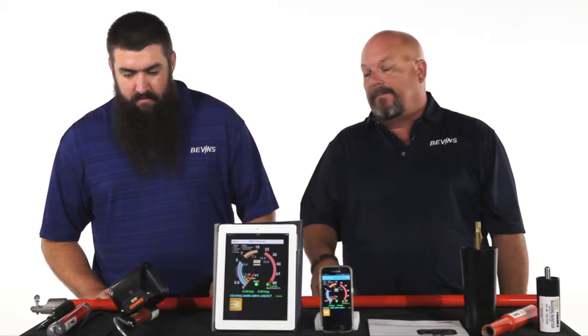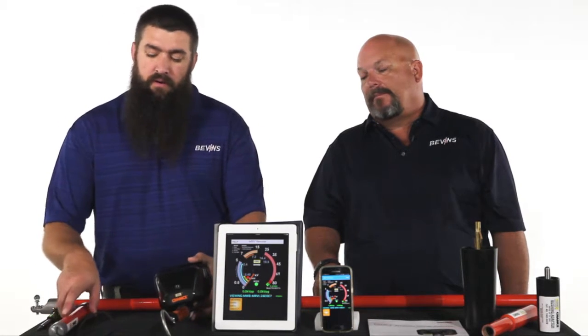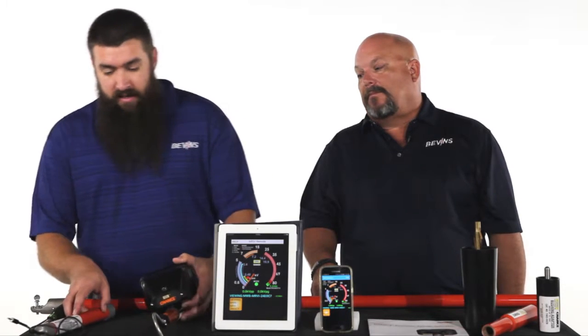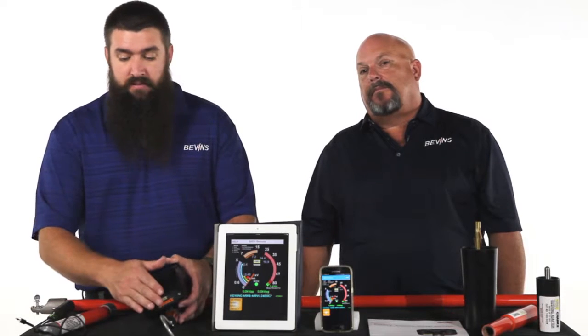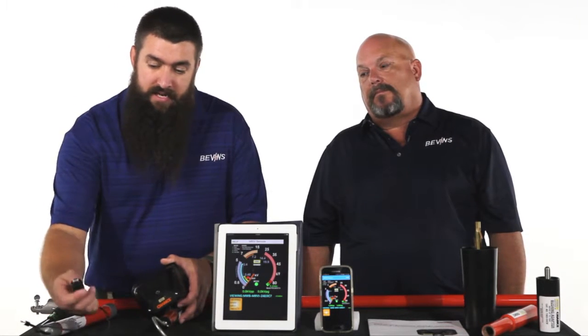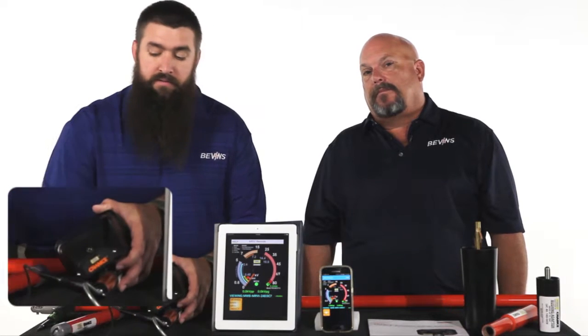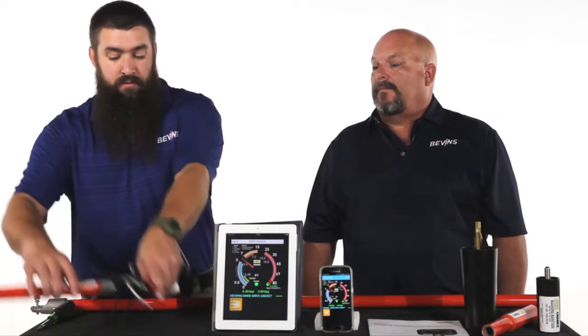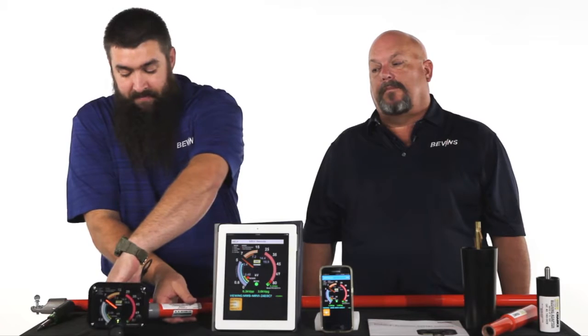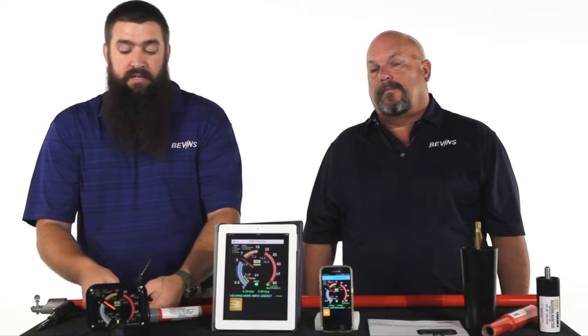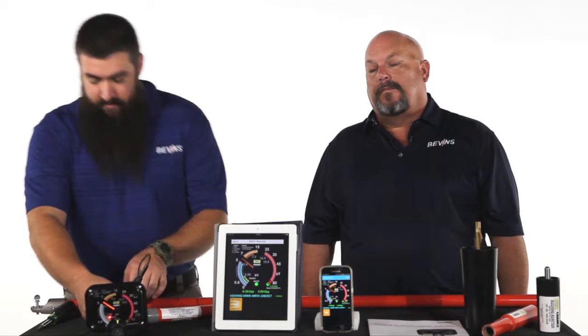Casey will describe how we hook up the field tester to test the MARVI. So we have our field tester here, model number PSC 4033582, and it has two connection points that need to be made to the unit. We need to attach the clip to the input probe of the MARVI, and attach the jack to the input on the meter housing here. When we do that, we're simulating a voltage signal into the unit. Just flip it around where you can see there. An operable MARVI should indicate voltage when hooked up properly to the field tester.